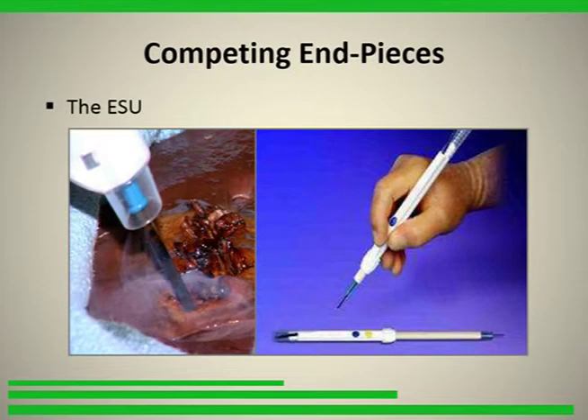This is a problem with the ESU pencil. You can see the tip of the tubing has to come fairly close to the tip of the electrode in order to capture smoke. But the problem is that if you do that, then the surgeon can't see the tip of the electrode and it's hard to operate. So they pull it back. When you pull it back, because the closeness of the orifice to the source of smoke is so critical to smoke capture efficiency, the efficiency drops off significantly as the ESU tubing is pulled away from the tip of the electrode.